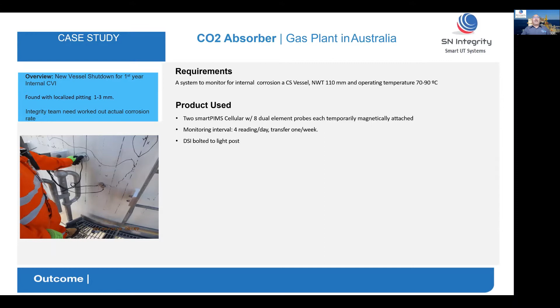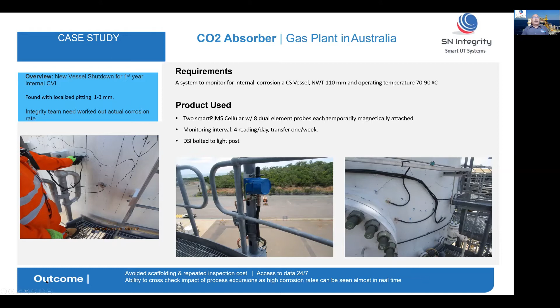And this is how the sensors look on each low point, and they have been installed since December 2019 with no issues whatsoever. So again, they save by avoiding scaffolding and repeat inspections, because they have access to data 24/7, and also the ability to cross-check the impact of process excursions almost in real time. They can then avoid this kind of corrosion that caused a high corrosion rate on that particular vessel.